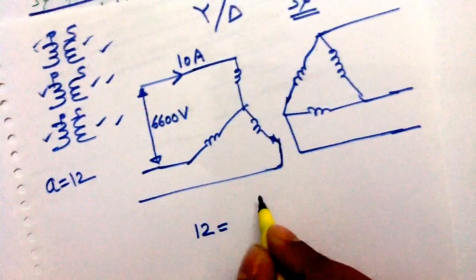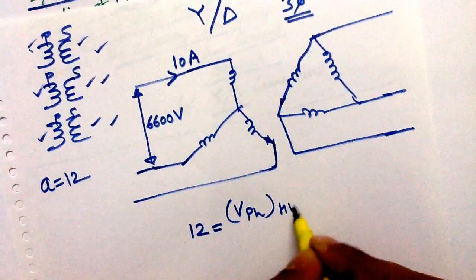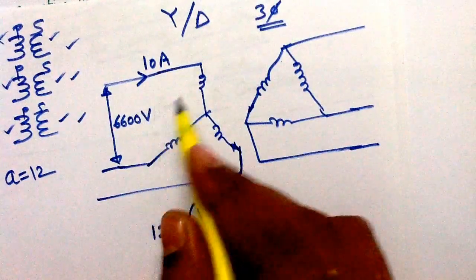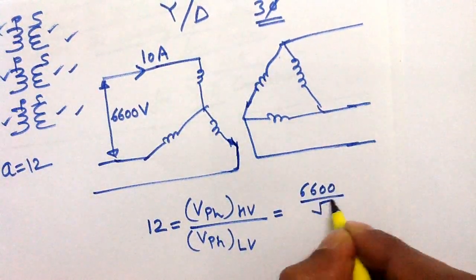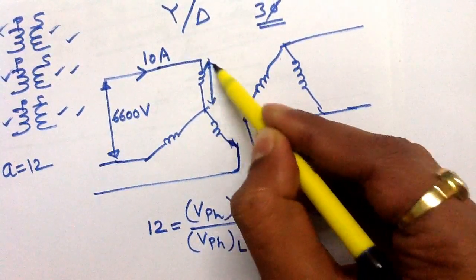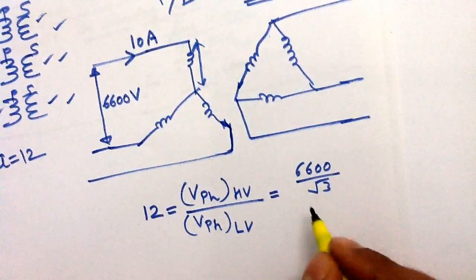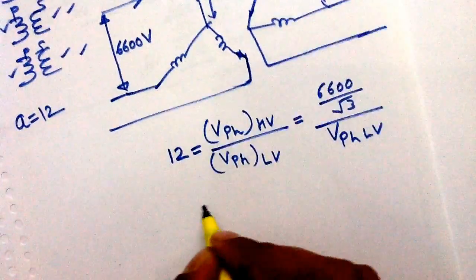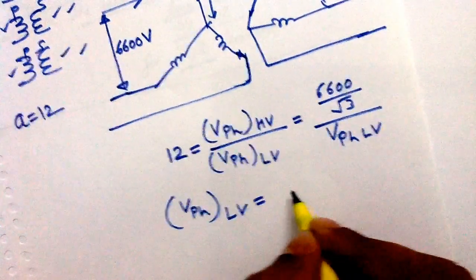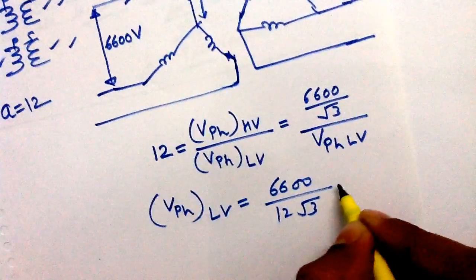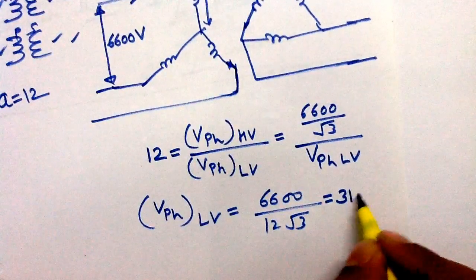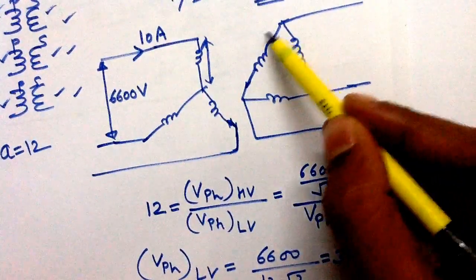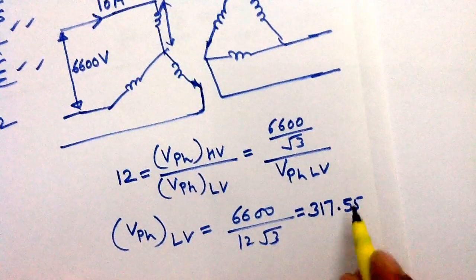The turns ratio equals the phase voltage of the HV side divided by the phase voltage of the LV side. The per-phase voltage of the HV side is 6600 divided by root 3, since the primary is star-connected. The per-phase voltage of the LV side will be 6600 divided by 12 root 3, which equals 317.55 volts.